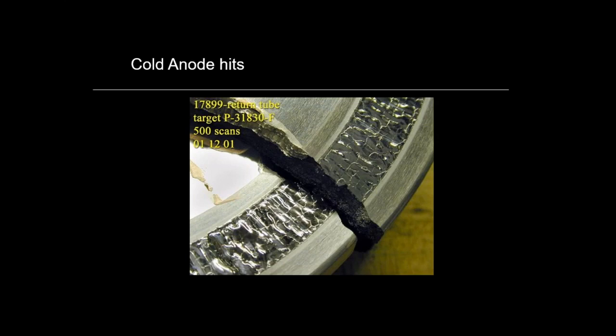And you can get that pitting anytime that stator is not running right, or your rotor board's going, or you have a short stator, or bearing is going. It's all about the speed. Yeah, speed and about the cooling. Sometimes they'll run for years. If you have a guy that installs it properly with the wrong rotor speed, it will wear off prematurely. And you don't even find it when you're flying around looking inside somebody's machine.